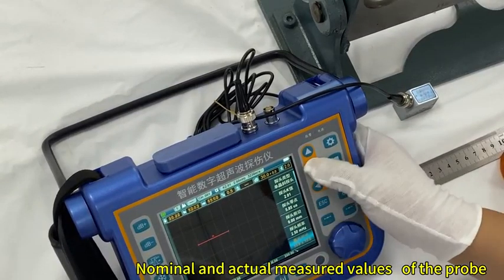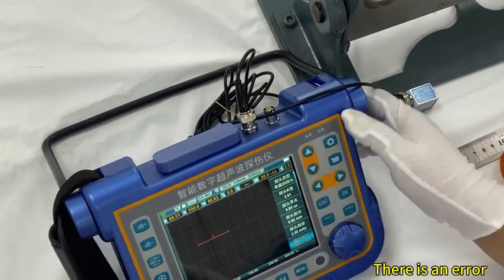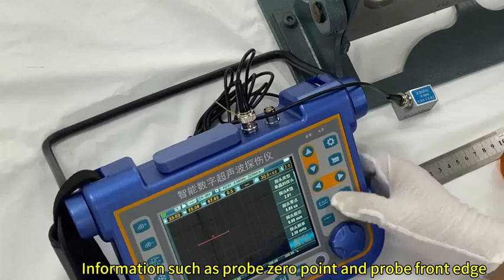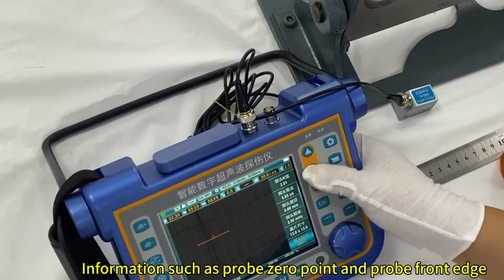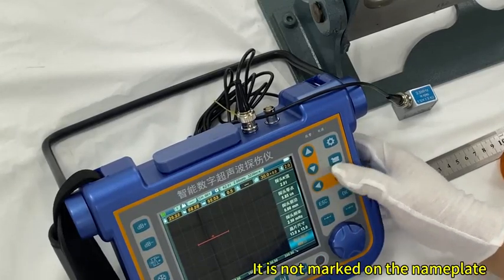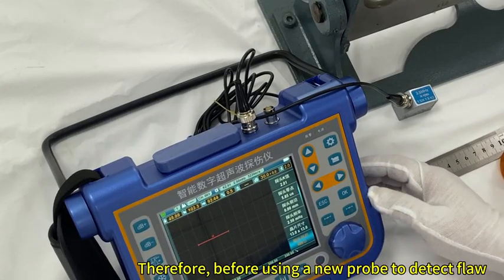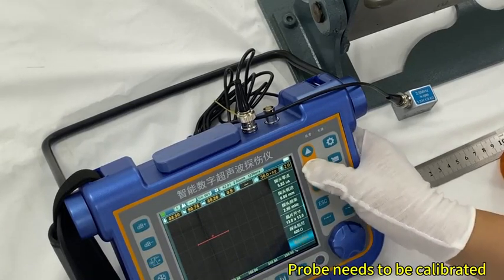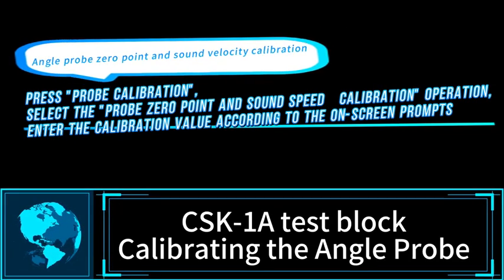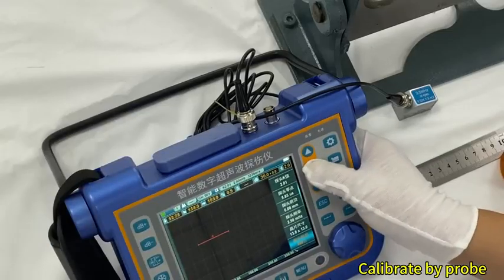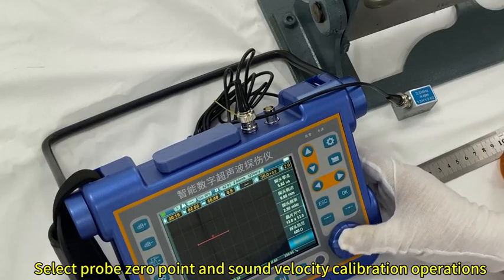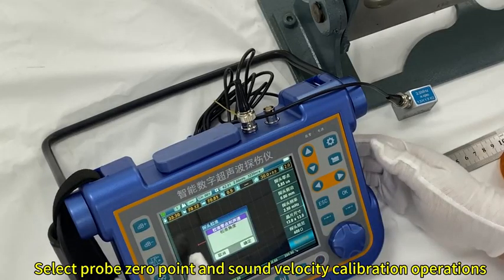The nominal and actual measured values of the probe have an error. Information such as the probe 0 point and probe front edge is not marked on the nameplate. Therefore, before using a new probe to detect flaws, the probe needs to be calibrated. Calibrate the probe. Select probe 0 point and sound velocity calibration operations.